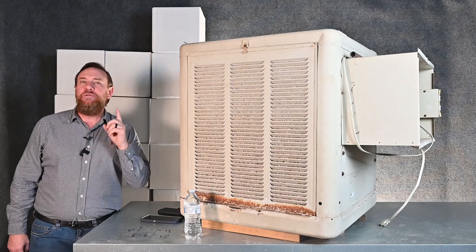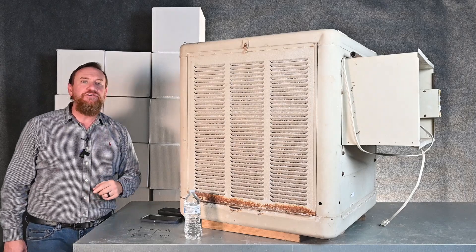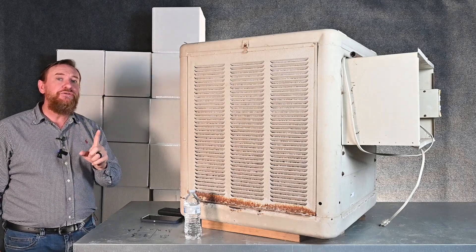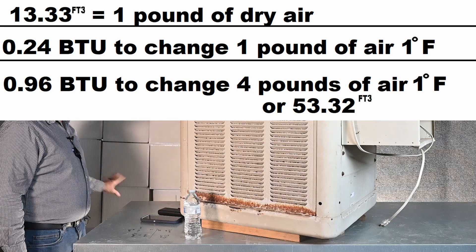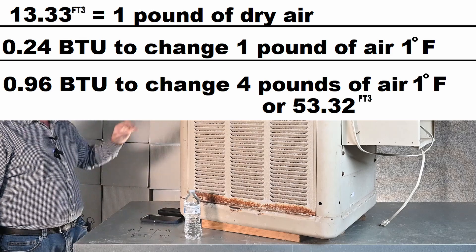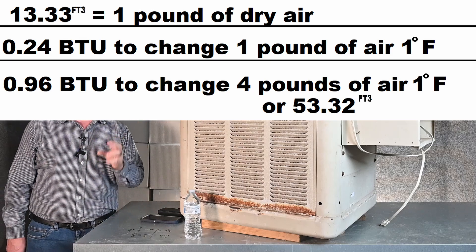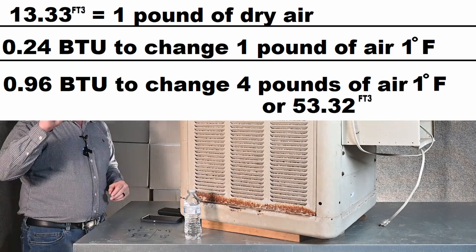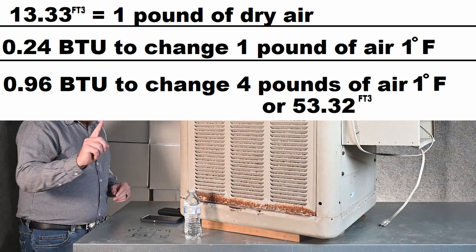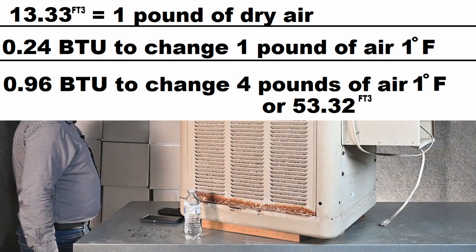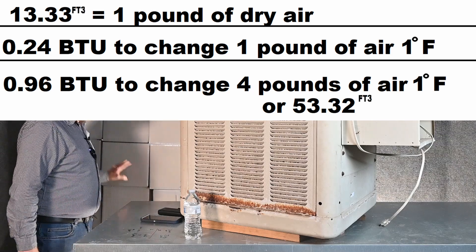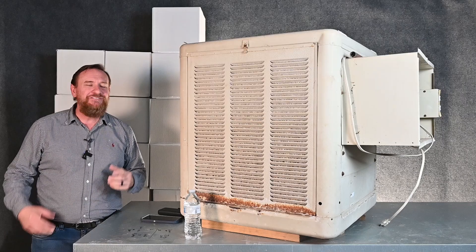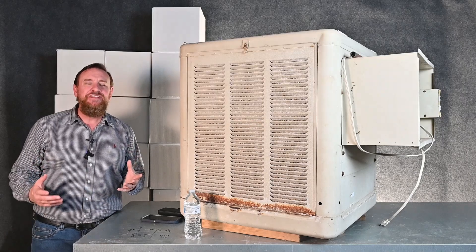Let's look at what 1 full BTU would do. If I had 1 full BTU, that would be 4 pounds of air — 4 times this much — it would also be 55 cubic feet of air. So only 1 BTU would change 55 cubic feet of air 1 degree Fahrenheit. It's quite impressive.